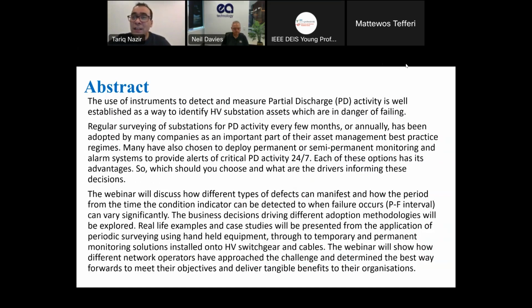Here is the abstract. The use of instruments to detect and measure partial discharge activity is well established as a way to identify HV substation assets which are in danger of failing. Regular surveying of substations for PD activity every few months or annually has been adopted by many companies as an important part of their asset management practice regimes. Many have also chosen to deploy permanent or semi-permanent monitoring and alarm systems to provide alerts of critical PD activity 24 hours, 7 days a week. Each of these options has its advantages. So which should be chosen? And what are the drivers informing these decisions?